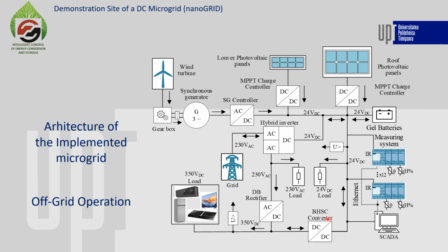Now, regarding the loads, as I said at the beginning, common electrical appliances such as an induction hob, a fridge, an air conditioner, and a TV were adapted for DC supply and are connected, as you can see, to the high voltage DC bus. The conversion was not so complicated given that all of them use diode bridge rectifiers as an interface with the AC grid. There were some specific problems, especially for the induction hob, for which it was necessary to emulate the grid frequency. That's because the grid frequency is used by the internal zero voltage switching resonant converter to achieve a higher power factor.